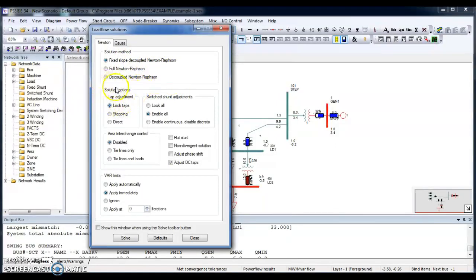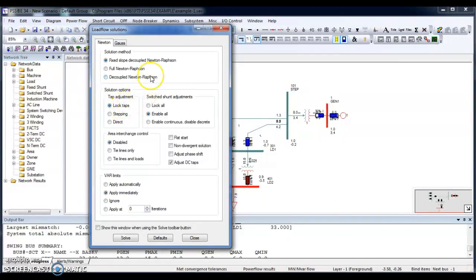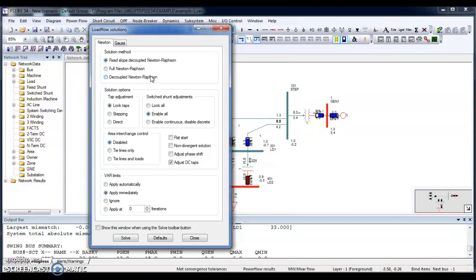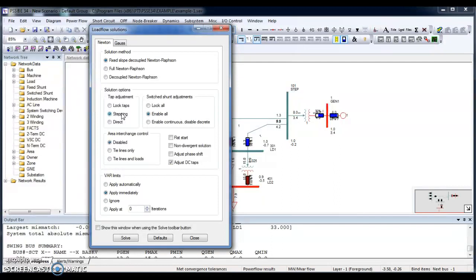So there are other options in solution options. If you see, there is a tap adjustment. What's the difference between the lock taps and stepping? The lock tap is you have fixed your tap of your transformer that will never be changed. Whatever the tap you have given to it, it will stay on that tap. If I go for stepping, it will make tapping and it will adjust the tap as the sizes you have given to that tap. But remember, when you have selected the tapping, you should select auto adjustment in the parameters of the transformers.